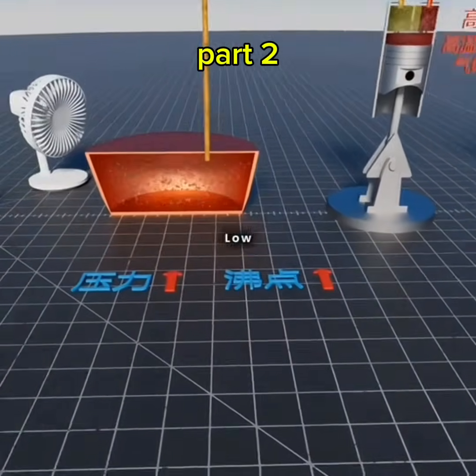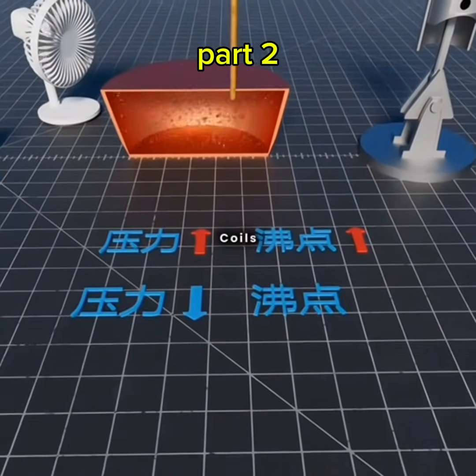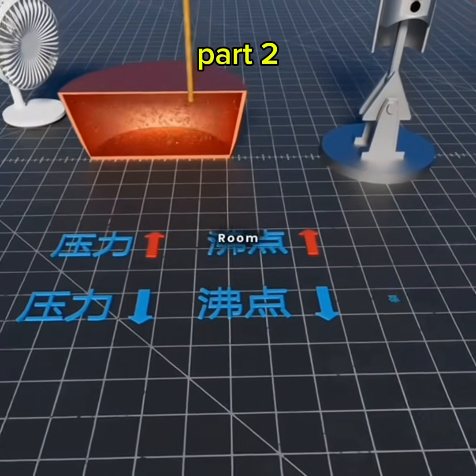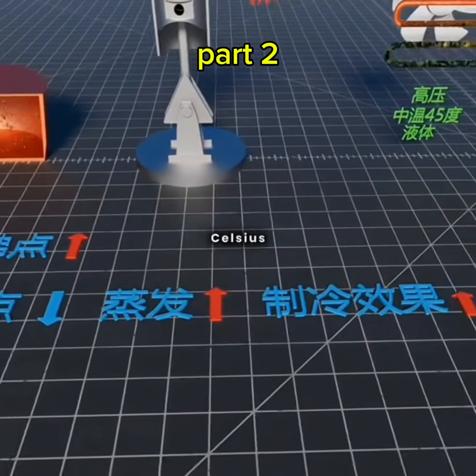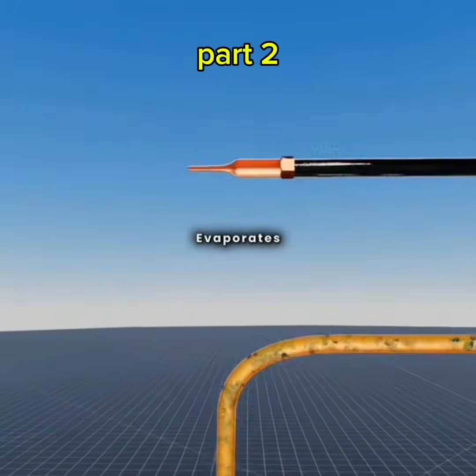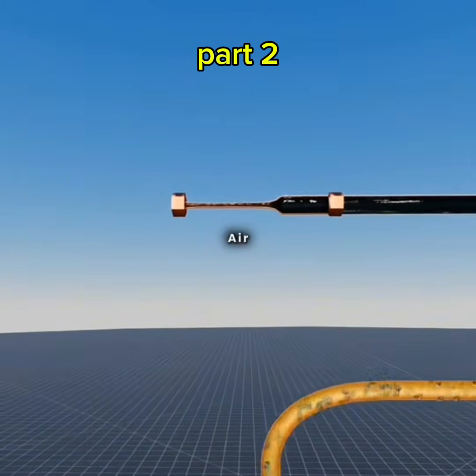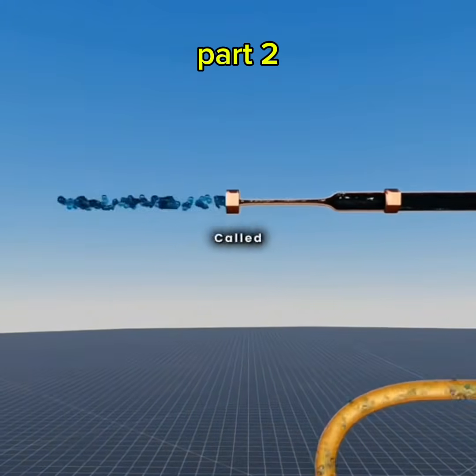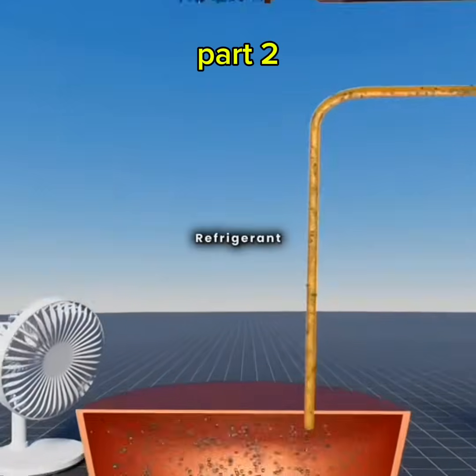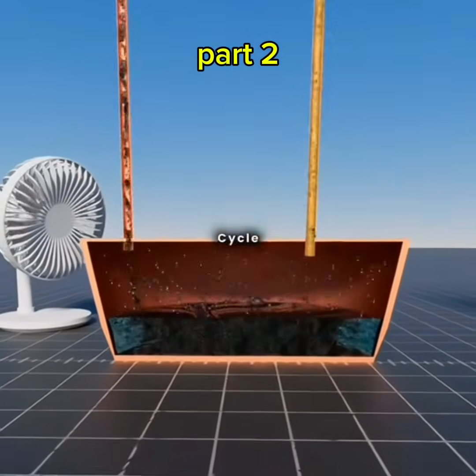You then send this low-pressure refrigerant into another set of coils inside the room. Since the room temperature is much higher than 5 degrees Celsius, the refrigerant quickly evaporates, absorbing heat from the indoor air and producing cold air. This part is called the evaporator. Finally, the refrigerant gas returns to the compressor, and the cycle starts all over again.